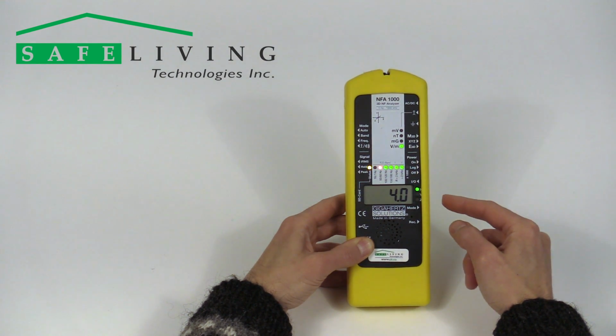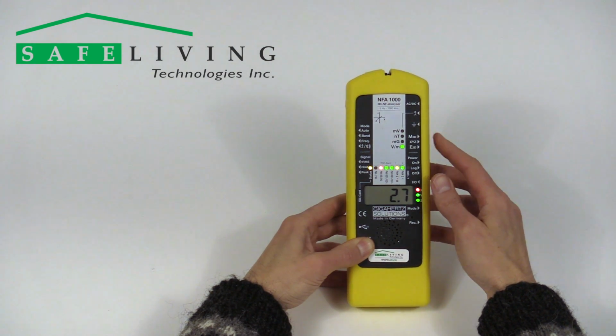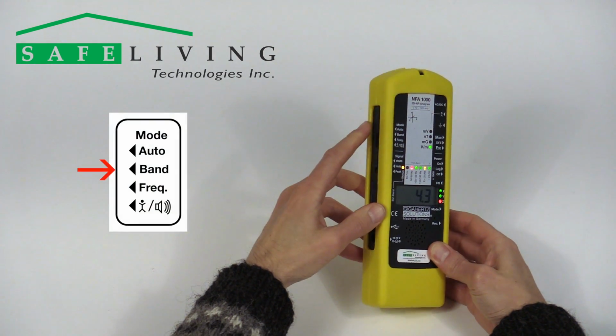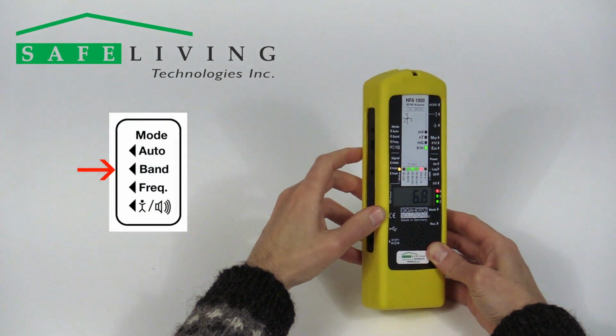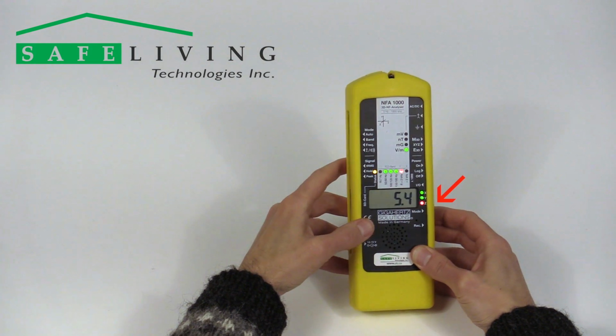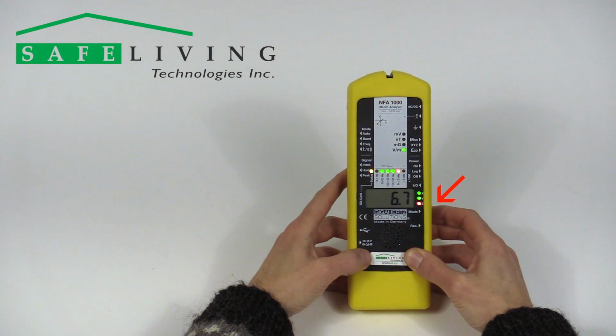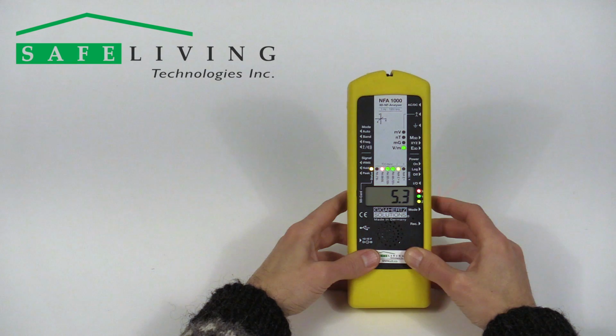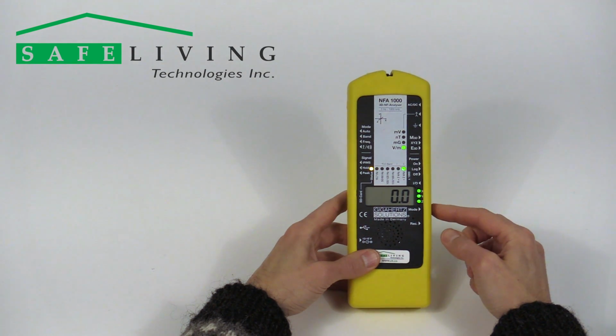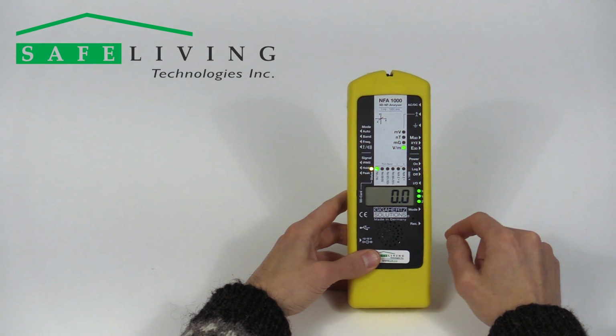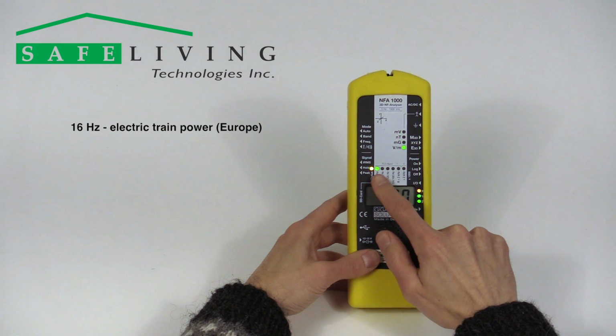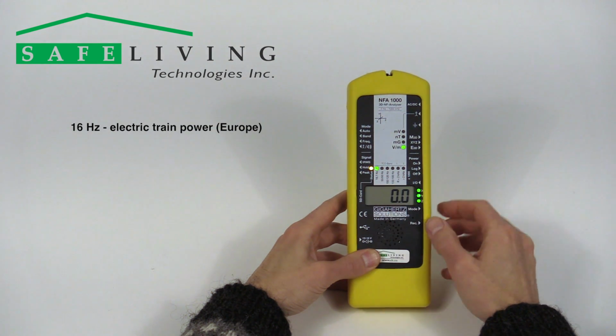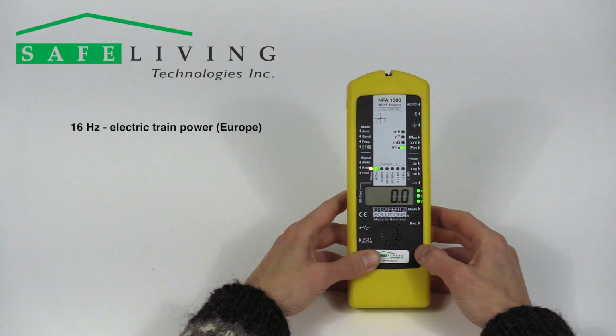If you would like to manually select a single frequency band range to measure, move the mode switch to band as shown. The mode button, shown here, now allows you to select which band or frequency range you would like to measure. Each single push cycles through the bands as follows.